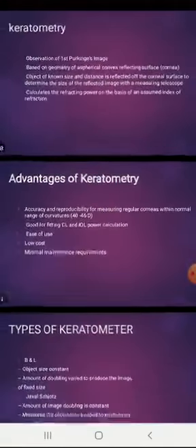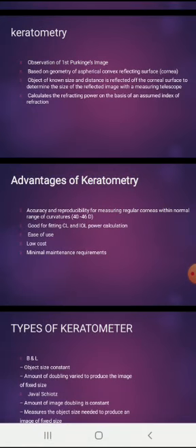Keratometry is mainly based on the size of the Purkinje image. There are four Purkinje images in our eyes, and the first one forms on the cornea. This image is the basic means for measuring the corneal radius of curvature as well as the corneal astigmatism of the patient by using the keratometer.